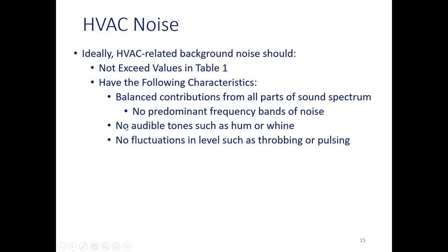Now we're getting more specifically into the tones. So this bullet point, no audible tones such as a hum or whine. Tones can be particularly annoying if you have other background noise, say it's an open office space and there's that hum of office activity. There's a tone or a whine from the HVAC system, like we talked about with that condensing unit, actually there were a number of condensing units, sitting right outside of a window, and its tone was the exact same frequency as the mass airspace mass of the glass. It just went right through it. That was an open office setting, and that tone was incredibly annoying to the people.